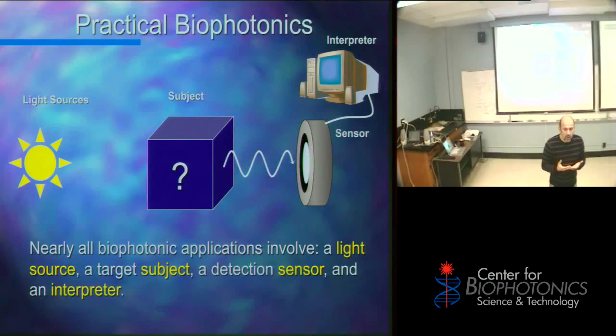And the thing is, you're not glowing in a wavelength that, if we turned off all the lights and this room was perfectly black, I could see you. Because my eyes can't detect the far infrared that you're emitting. But that little device can. And it matches it to something called a black body radiation curve. That curve is very, very sensitive to temperature variations. It's temperature to the fourth. So a small change in temperature makes a big change in what this senses. It takes 3,000 readings in the time you swipe it across your forehead and figures out the highest temperature it measures. Now, it's not measuring the temperature of the surface of your skin, what is it measuring?